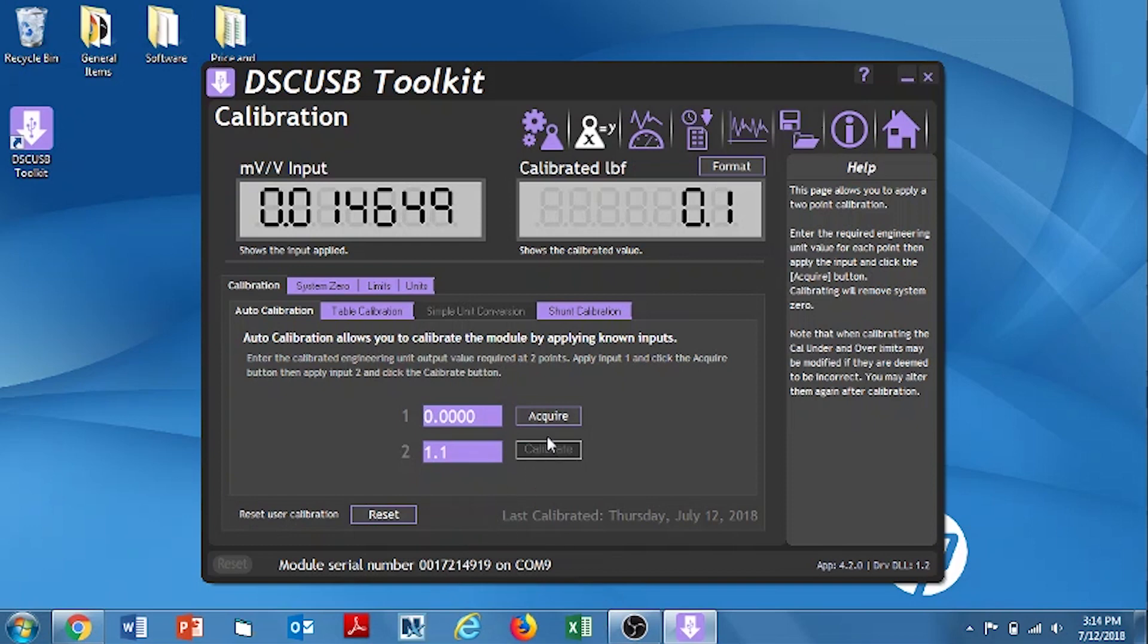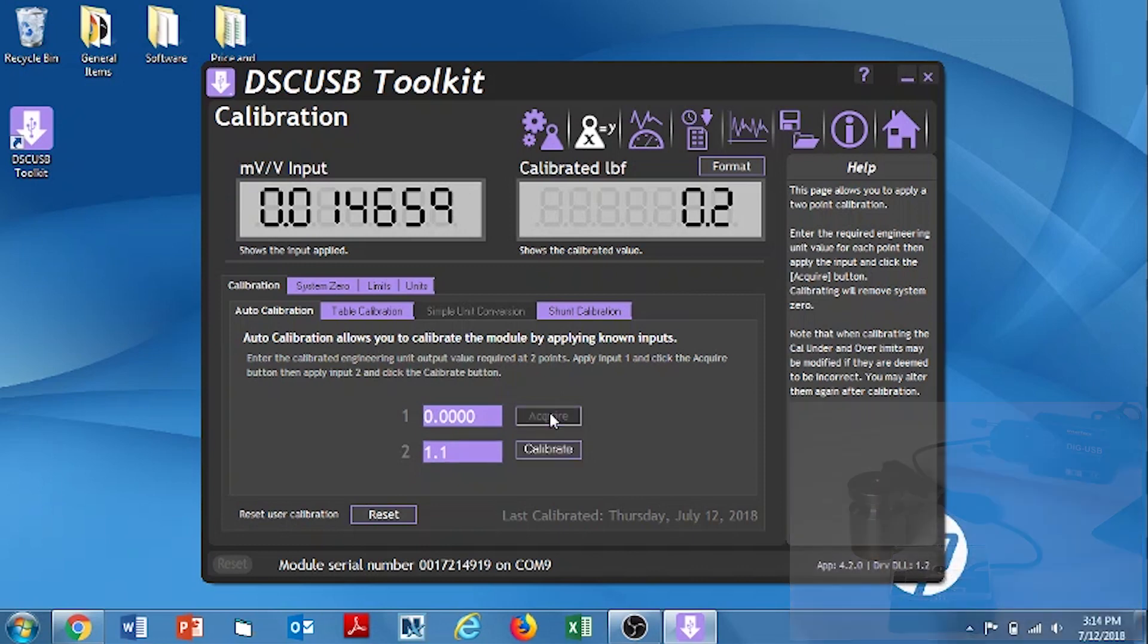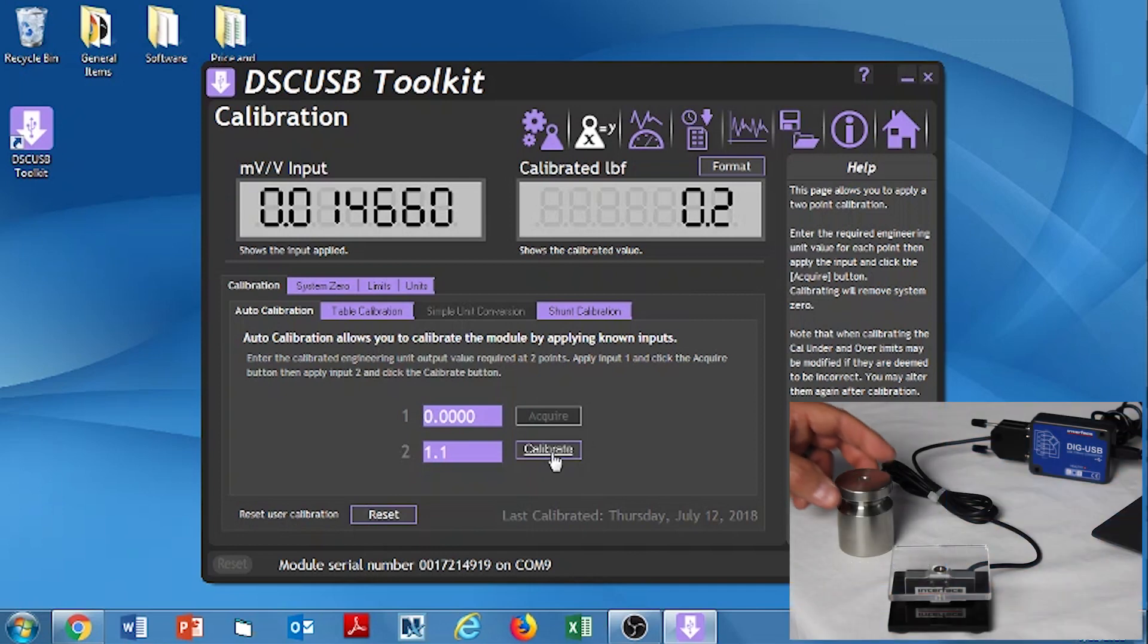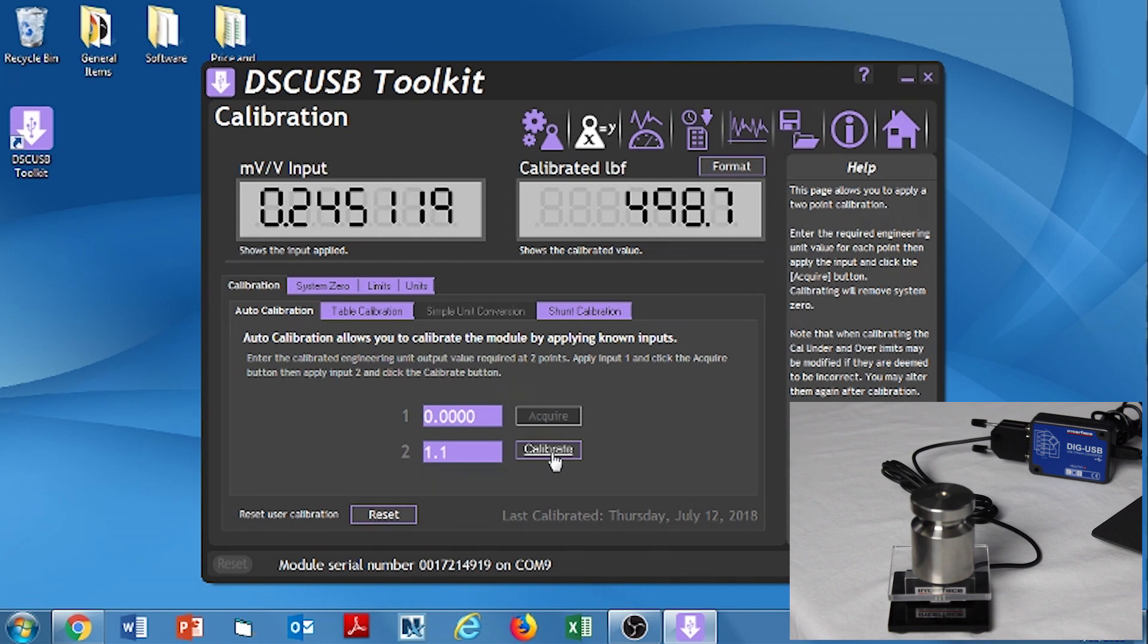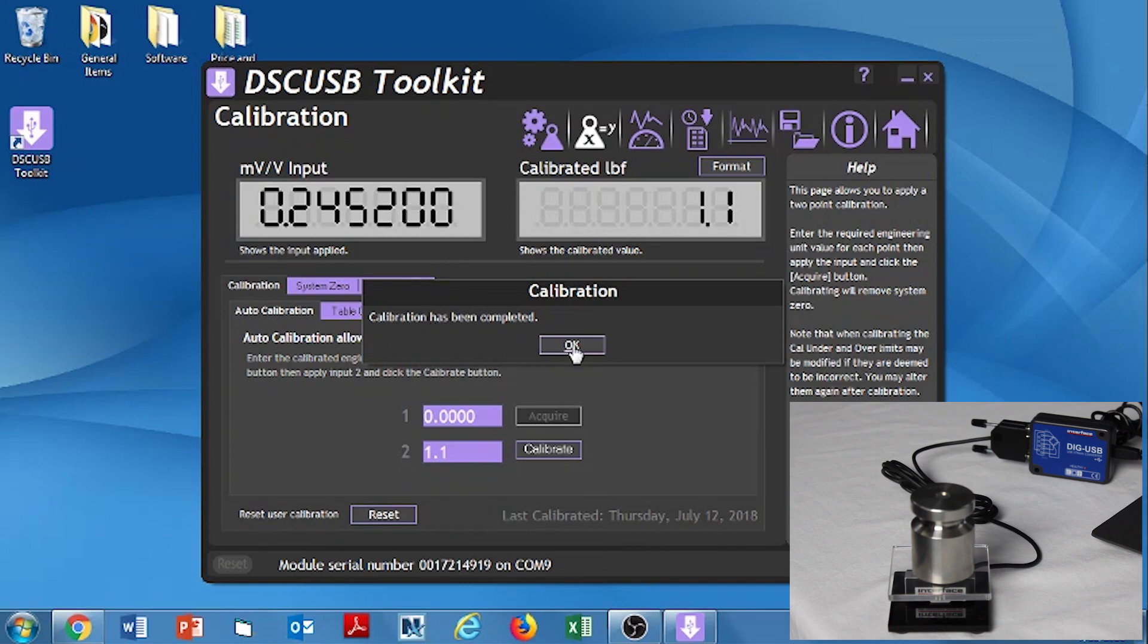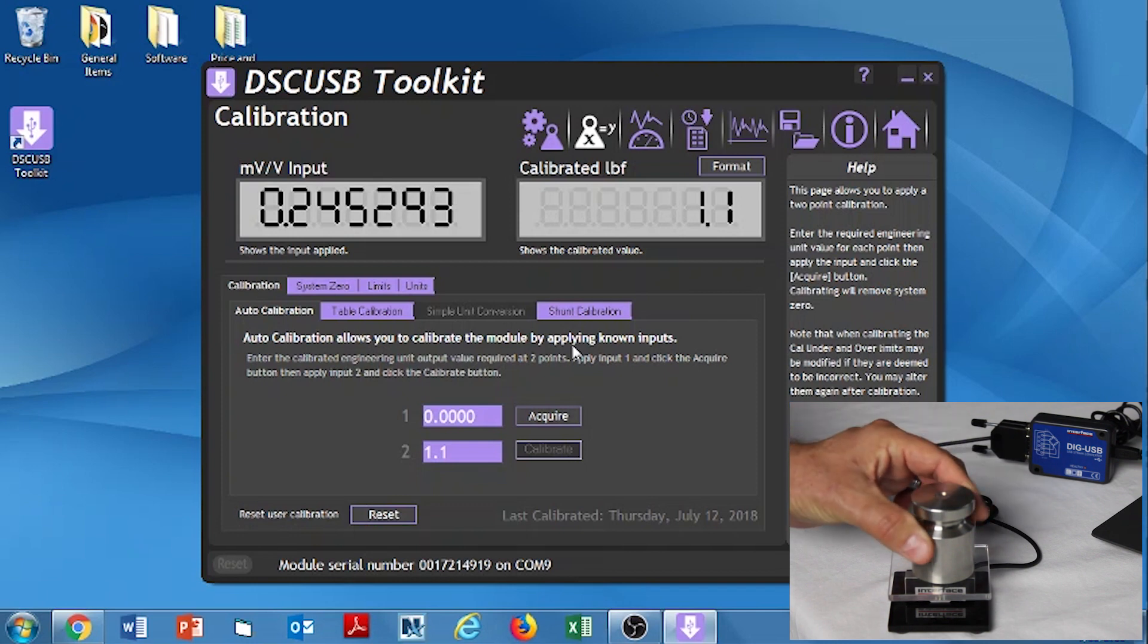So, make sure the table is nice and stable. And the scale is unloaded. And hit Acquire. Once it's acquired that, it goes dark. And it's ready for the next cal point. The next cal point is to load our 500 gram or 1.1 pound weight onto the load cell. And I click the calibrate button. And it says calibration has been completed. We click the OK button. Now we can remove the weight.